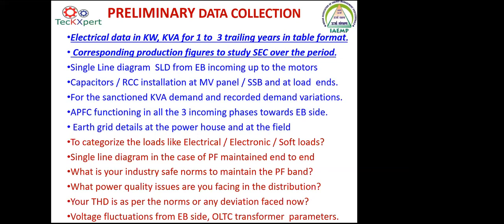And then is the power quality in the distribution, how much it is taken care of at the distribution, at the incoming and at the load ends. The THD norms, is it as per the norms, or is any deviation there on the voltage side and the current side, and what can be done. These are all the discussions you have to have in the opening meeting with your energy auditor once he comes and sits in your premises.